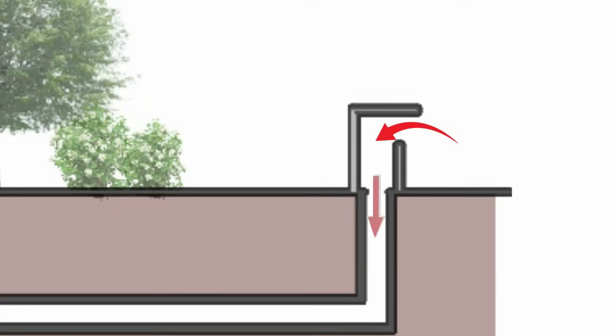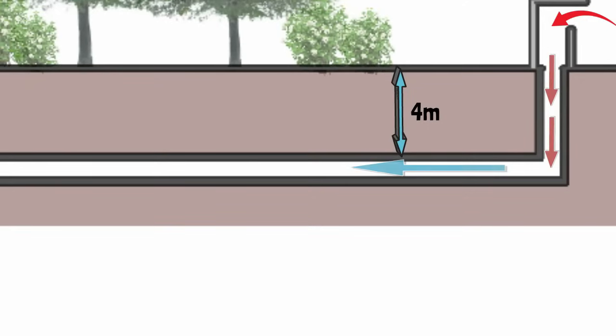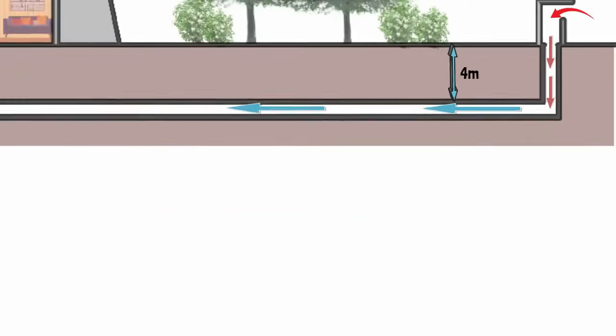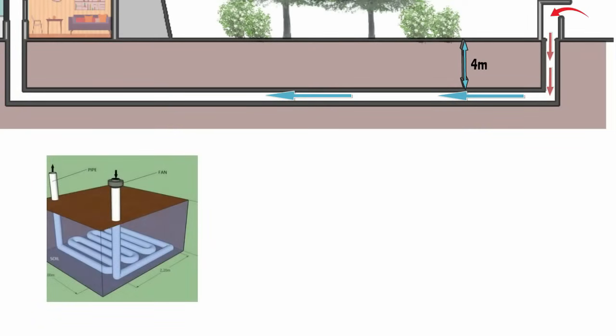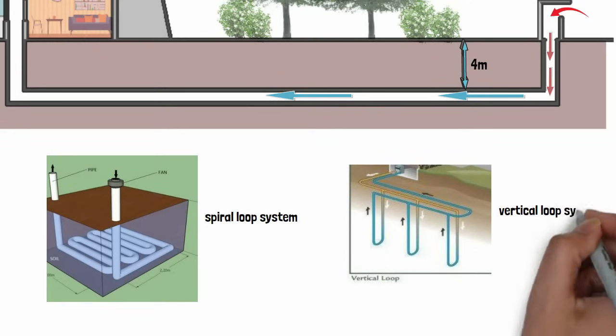The duct pipe is laid down 3 to 4 meters below the surface, which also depends on soil properties and water content. Higher length means increased heat transfer and higher efficiency, but it also makes it less economical. There are different kinds of loop systems, such as vertical and spiral loop systems, which improve efficiency.